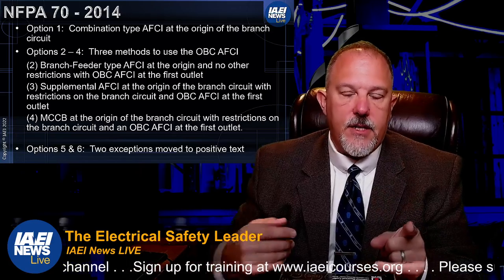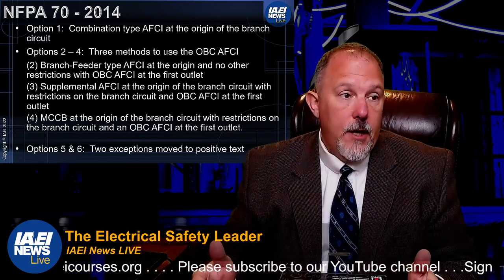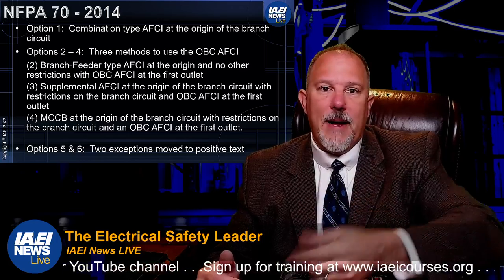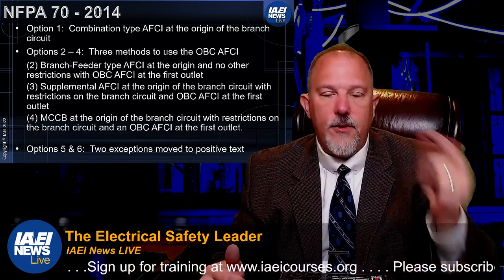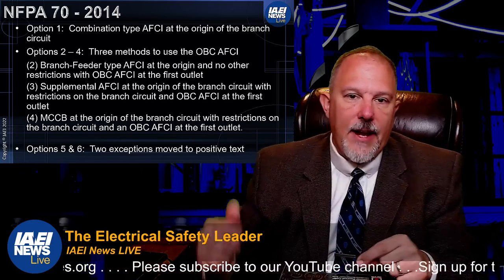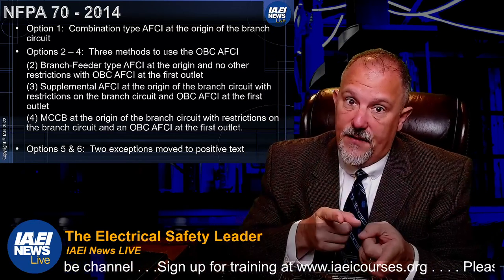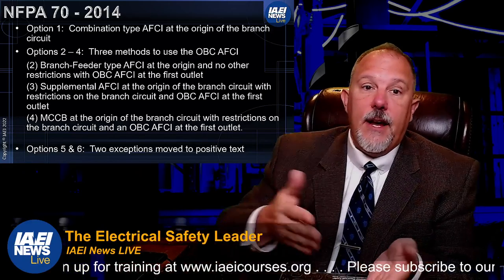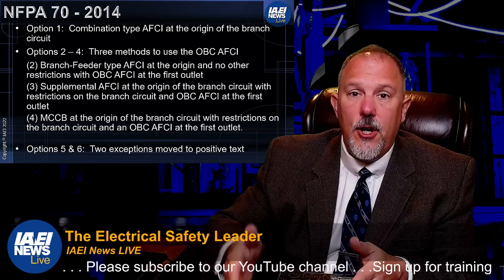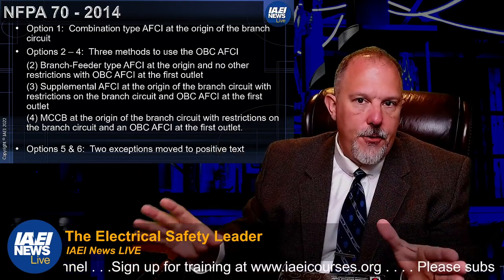Option one is the combination type AFCI at the origin of the branch circuit. This is not new — it's been a requirement since the beginning, just updated from branch feeder to combination type in the 2005 code with an enforcement date of 2008. Any structure built to the 2008 NEC or later would already meet option one. Options five and six — the OBC with a protected home run in raceway or concrete — were moved from exception language into positive code text.